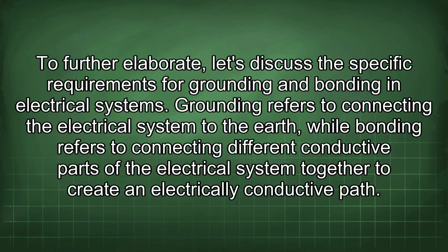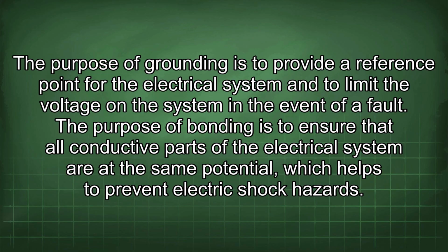To further elaborate, let's discuss the specific requirements for grounding and bonding in electrical systems. Grounding refers to connecting the electrical system to the earth, while bonding refers to connecting different conductive parts of the electrical system together to create an electrically conductive path. The purpose of grounding is to provide a reference point for the electrical system and to limit the voltage in the system in the event of a fault. The purpose of bonding is to ensure that all conductive parts of the electrical system are at the same potential, which helps to prevent electric shock hazards.